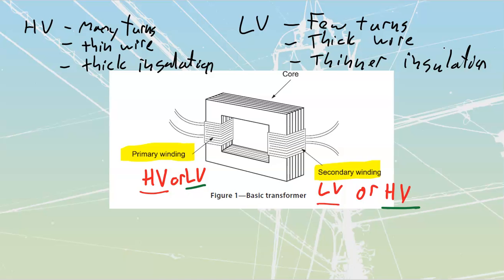The core itself is going to be made up of laminated pieces of iron. The reason for the laminations is to cut out any sort of circulating eddy currents. We know that we do have flux lines inside here. Those flux lines are cutting through here. If we're going to use iron, we want to use iron or something like that, so it's going to be a high permeability and a low reluctance.